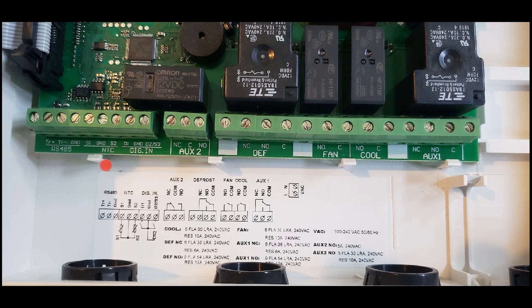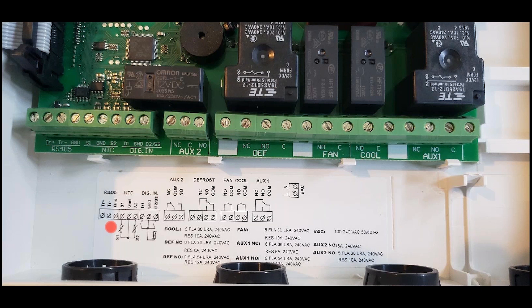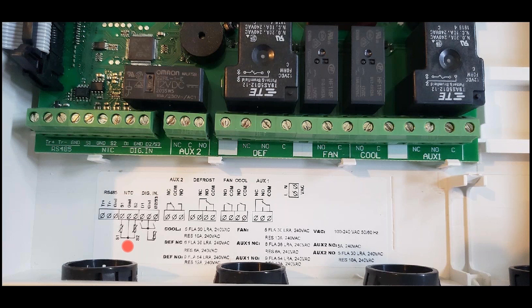Next, as you mentioned already, you have your sensor input. One sensor is used for off-cycle defrost because you do not need a second sensor to measure your evaporator temperature—you just allow the space air to defrost it during the time that it is not operating. If you do select electric or hot gas defrost and you want to have temperature termination or temperature initiated, you will need to use that S2. Now keep in mind it's important that ground you see here is common between S1 and S2.